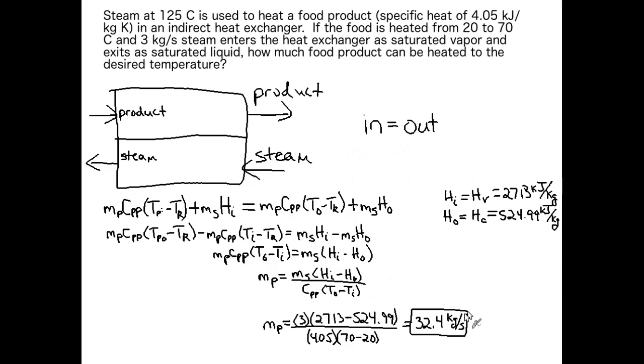So that's a very common mistake—to assume that all of the energy that's in your steam vapor goes over to your product side to heat it up, and that's not true because we are just changing phase. We're not cooling our steam all the way down to absolute zero. At absolute zero our steam enthalpy is zero, and since I can't think of a process that actually does that, our condensate is definitely going to have some enthalpy.